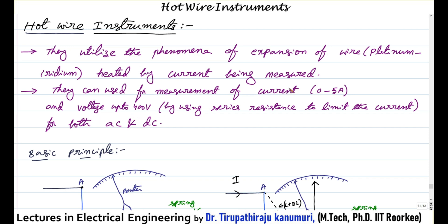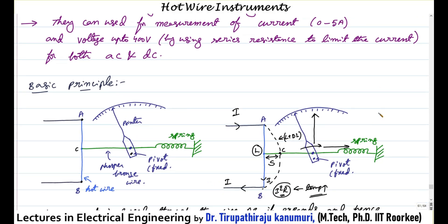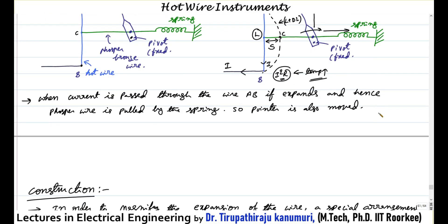Generally they are practically used mainly for current, very rarely for voltage. If you want to use for voltage, they can be used up to 400 volts, provided we connect some series resistance to limit the current. They can be used for both AC and DC because they mainly depend on the heating principle, proportional to current square, so they depend on the RMS value.